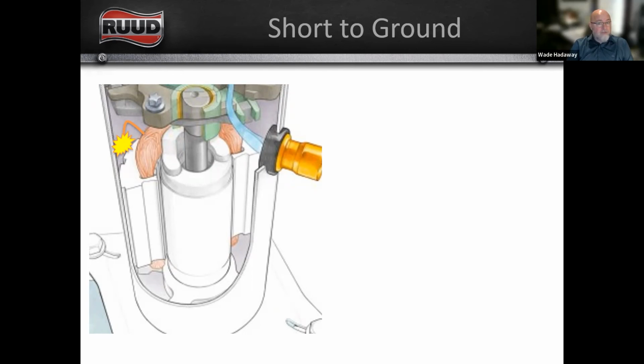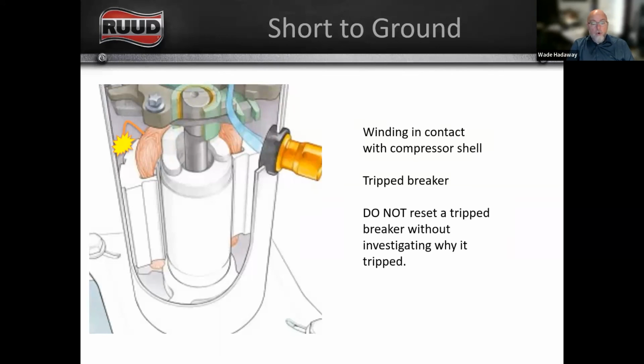It should. If this unit is not grounded properly, it should still trip the breaker, but it might not. So in this case, this unit could be electrically charged. That's why you want to be careful to not just walk up to a piece of equipment and lean against it. If you walk up to a unit on a service call and the breaker is tripped, either the breaker on the disconnect, if it's a fused disconnect, or the breaker at the panel, do not reset a tripped breaker without pulling out your meter and investigating why this breaker is tripped. It tripped for a reason. It is not a fluke. It is not an accident. Make sure you know why the breaker got tripped.